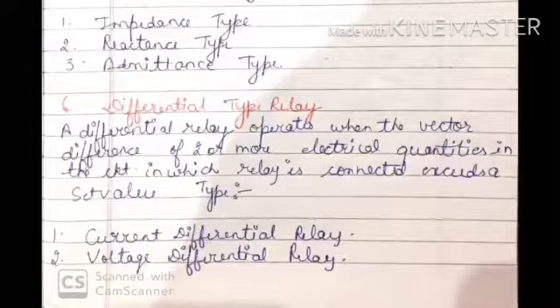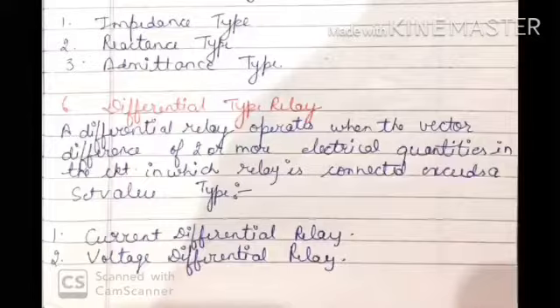Under fault conditions, the currents entering and leaving are different, so the current differential type relay operates. In the voltage differential type, two transformers are used, connected with the relay such that the induced EMFs are in opposition under normal condition. Under fault condition, the primaries carry different currents, due to which the induced EMFs no longer remain in opposition and the relay operates.